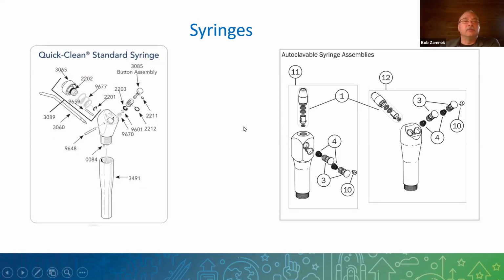One little trick we use in the service department: if we don't have the kit for your specific syringe on our van, or you don't have it in stock in your office, you can swap the valves out, putting the air valve into the water valve spot and the water valve into the air valve spot. It's a little better to have a bit of air leaking than water leaking.